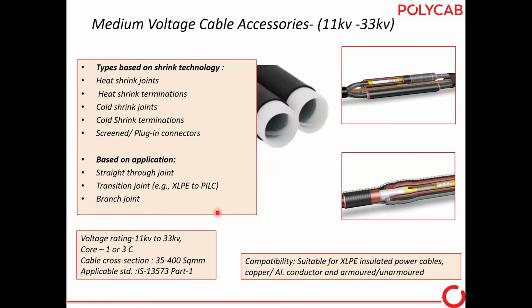Let's see the medium voltage cable accessories now. Medium voltage cable accessories are there for 11 kV, 22 kV, 33 kV. The types are based on the technology: heat shrink joints, heat shrink termination, cold shrink joint, cold shrink termination, and screened plug-in termination. Nowadays, screened or plug-in joint terminations are many times used wherever GIS or RMUs are there. Their customer uses the screened or plug-in termination.